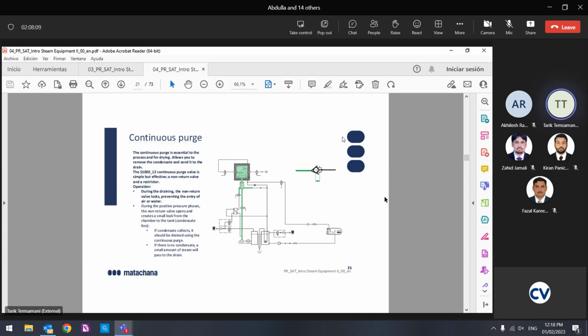In the case of the chamber, it's different. We have an electrical valve. We activate it electrically, it opens, and there is a restrictor. The restrictor has a small diameter, to remove only a small quantity of water. This one is activated with this valve. At the moment of the steam injection, I open it and I remove the water. And this one works with temperature. I detect cold temperature, I open to remove the water. I detect steam, high temperature, I close, and I have only steam here in the chamber. Okay, clear?